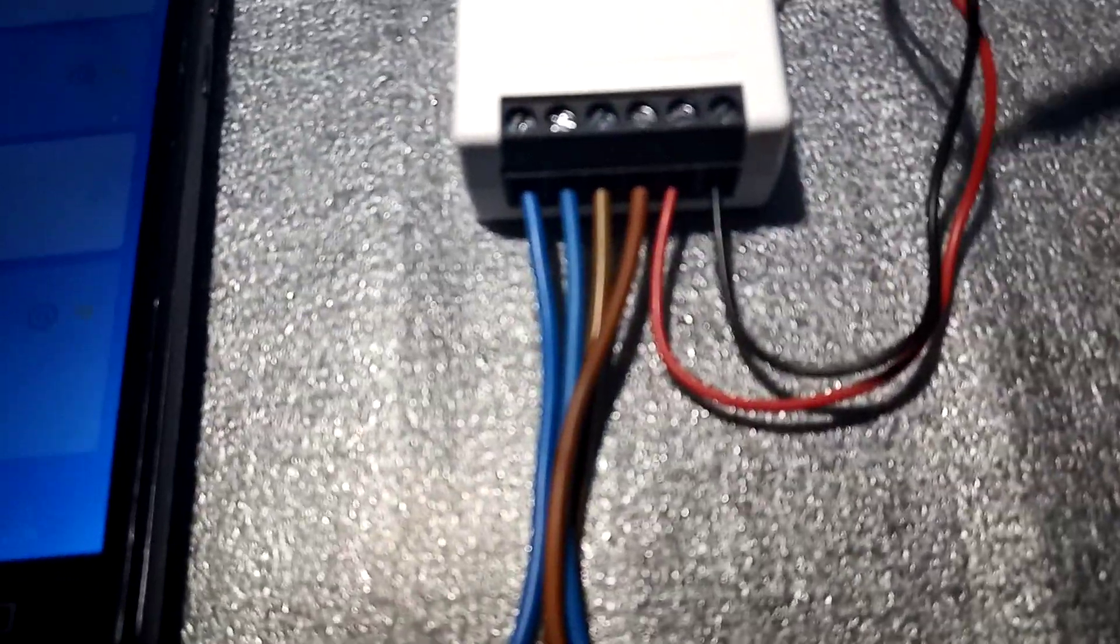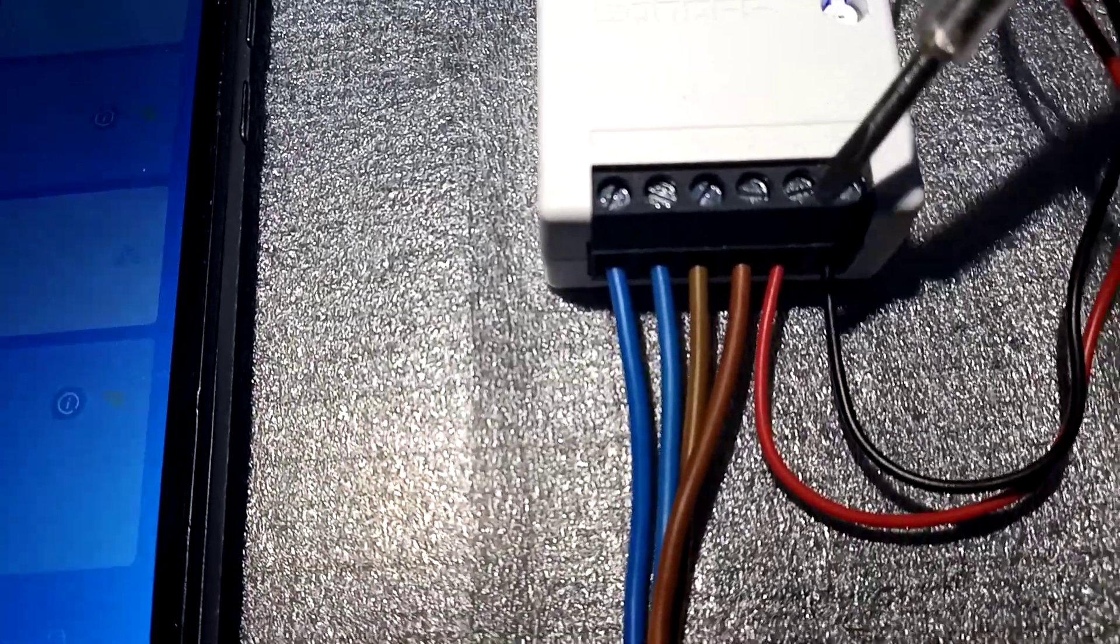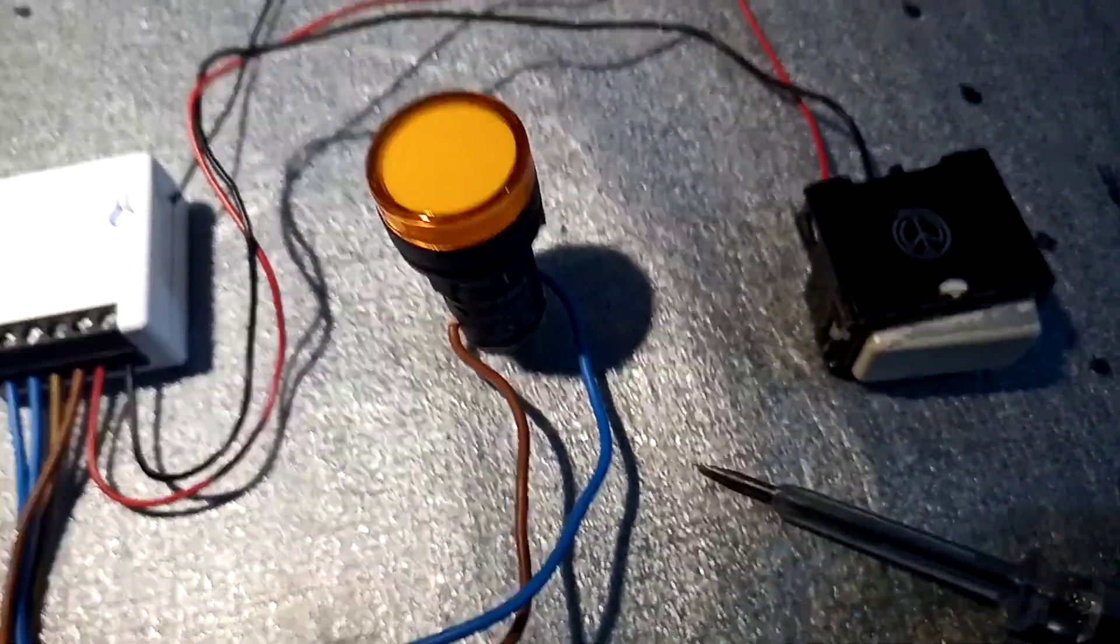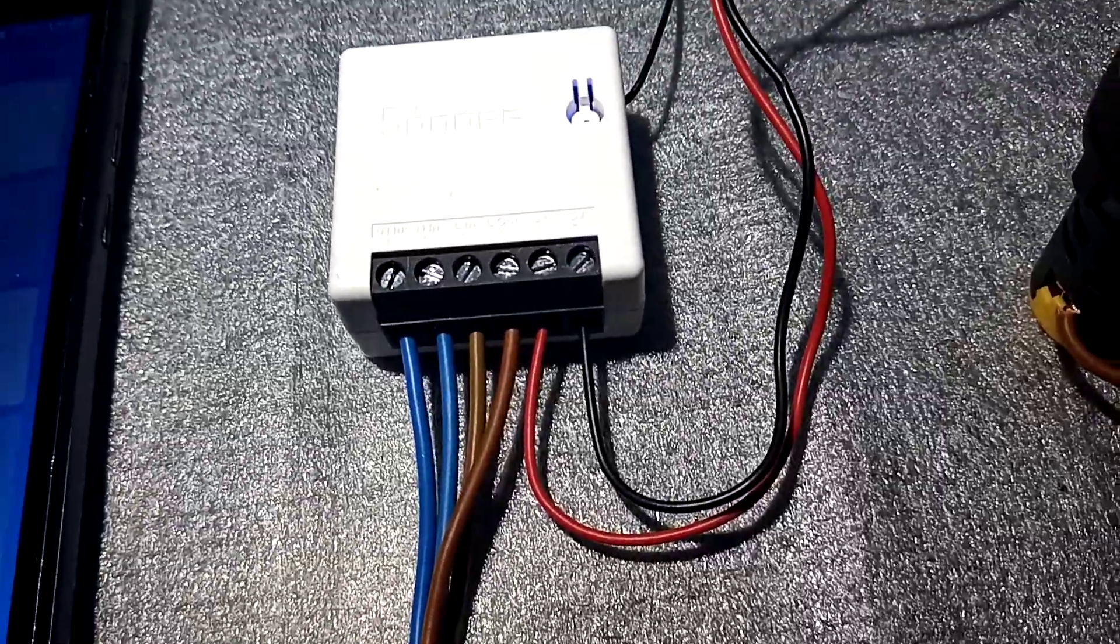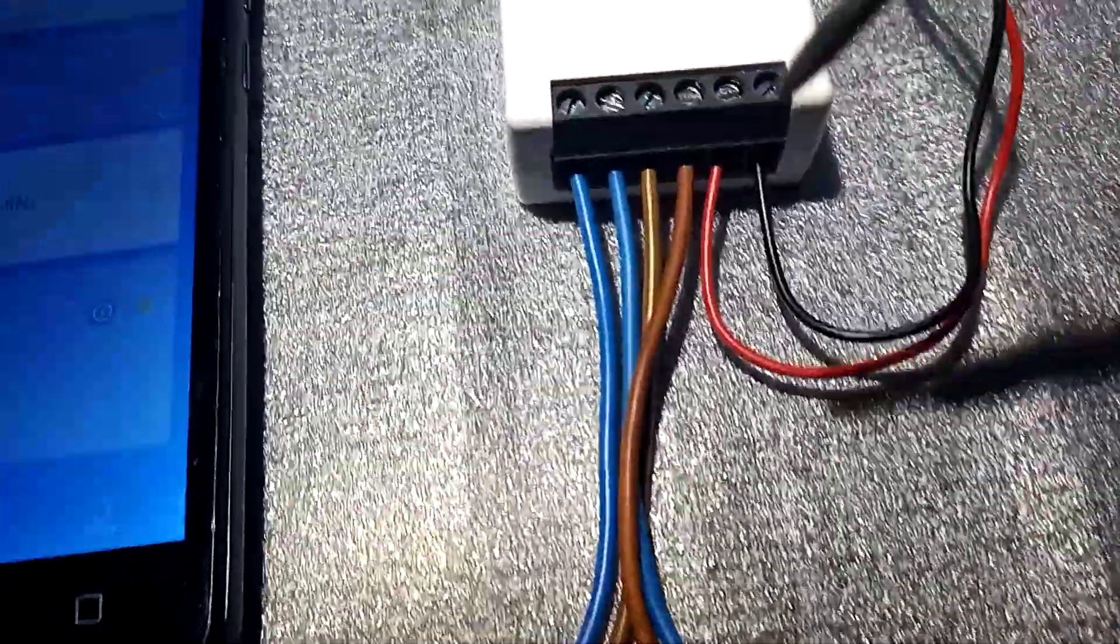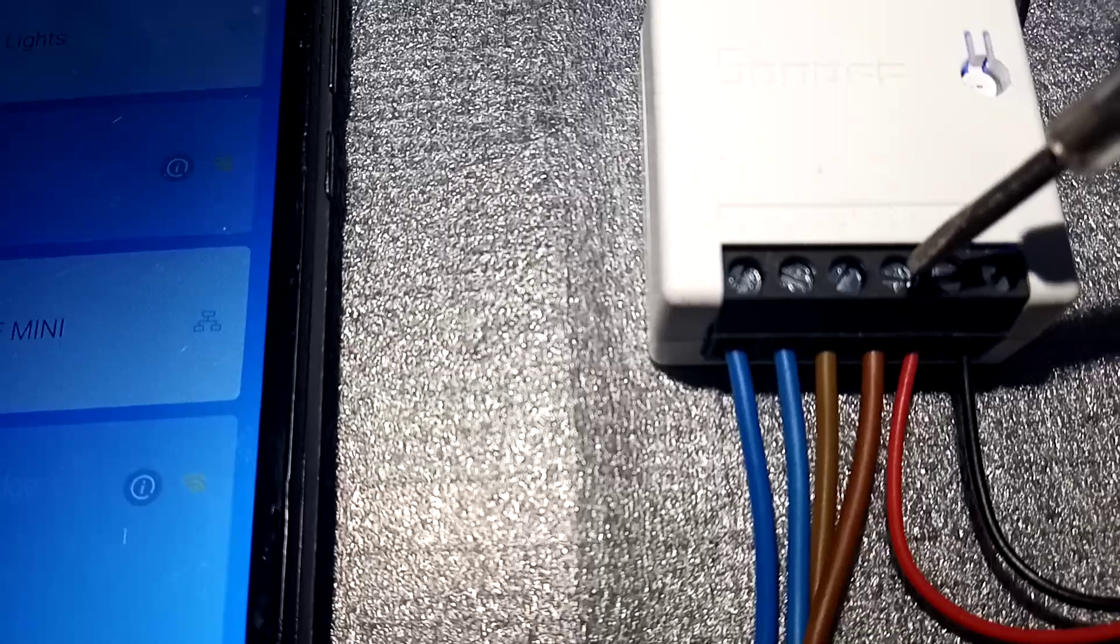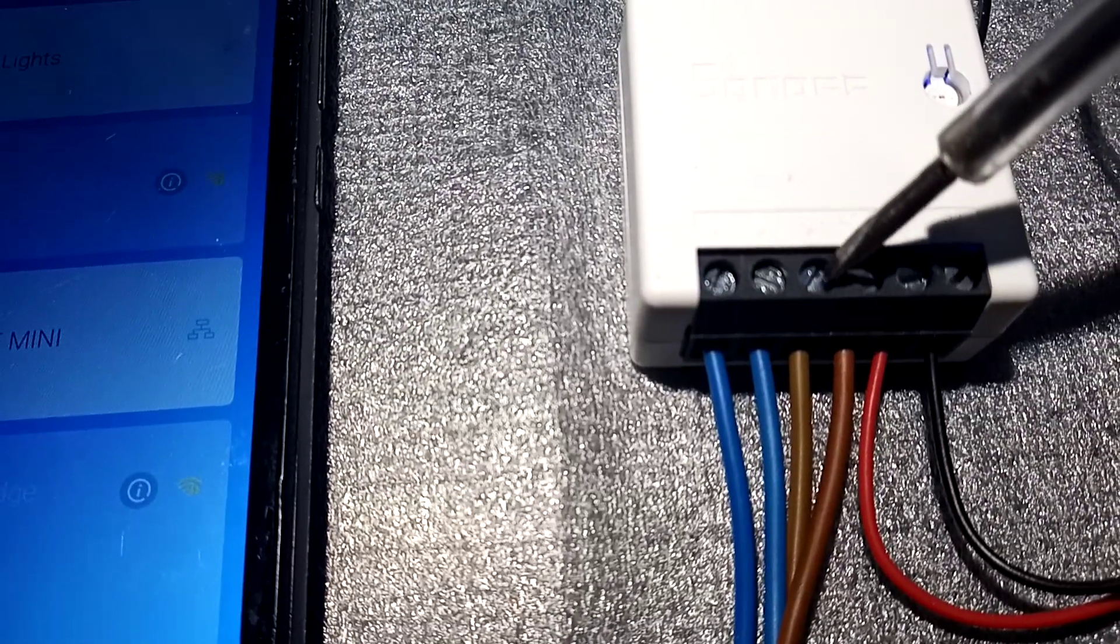Basically what we've done here is I've got these two wires coming out from the S1 and S2 switches, and they're going straight to my one-way switch. Then I've got the wiring done for the lamp. What's coming out of the Mini is this L1 out, then we've got neutral, neutral, and this is a live.